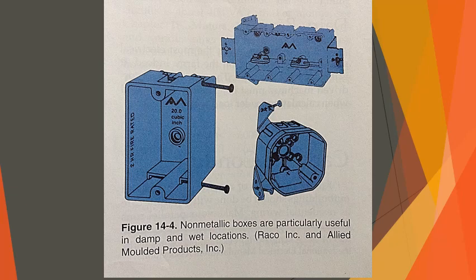For this reason, metallic sheathed cable and metal conduit are not suitable for farm wiring systems. Again, metallic sheathed cable and metal conduit are not suitable for farm wiring systems. Too often, the metal corrodes and weakens the ground, creating a hazardous condition. To ensure proper grounding and safe wiring in farm buildings, metal equipment is used as little as practical. Non-metallic cable, such as NMC and UF, and non-metallic outlet boxes, such as the ones shown in Figure 14-4, are preferred.